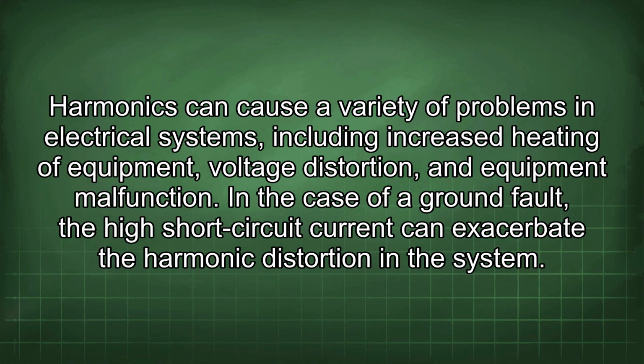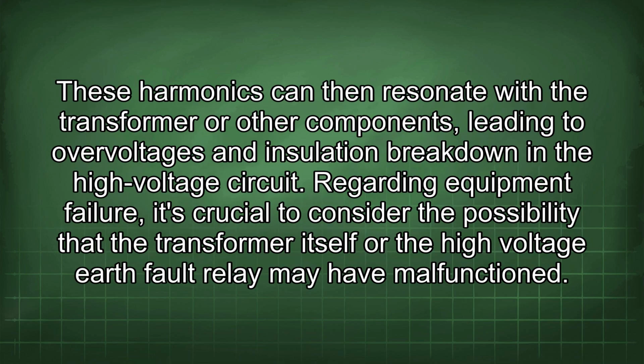In the case of a ground fault, the high short-circuit current can exacerbate the harmonic distortion in the system. These harmonics can then resonate with the transformer or other components, leading to overvoltages and insulation breakdown in the high-voltage circuit.